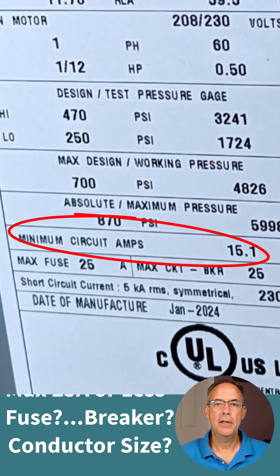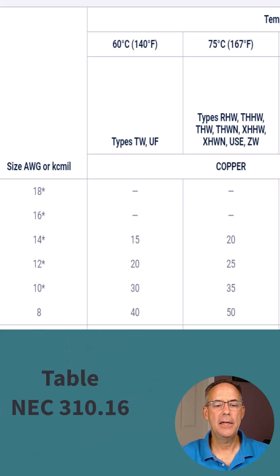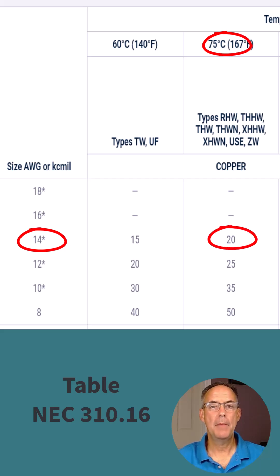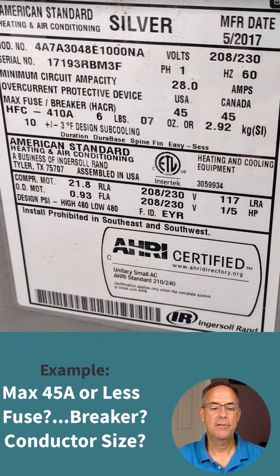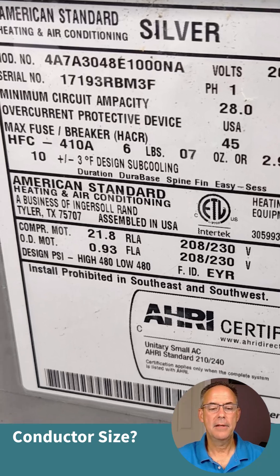The tag tells us the minimum circuit ampacity is 15.1 amps. If we go over to Table 310.16 and look at a number 14 conductor, a number 14 is able to carry 20 amps, so number 14 would be acceptable for that installation for our minimum circuit ampacity.